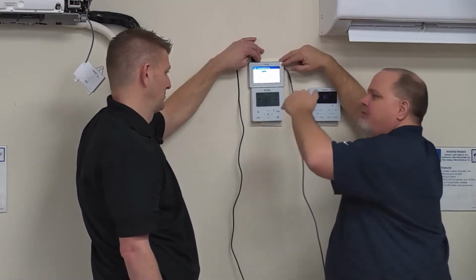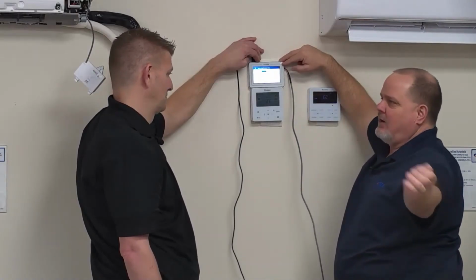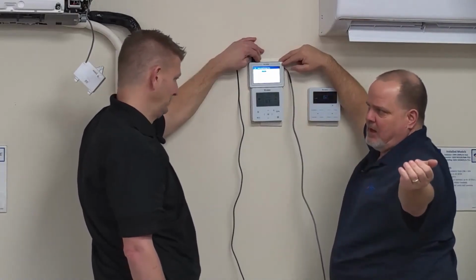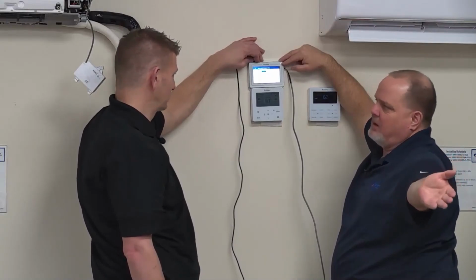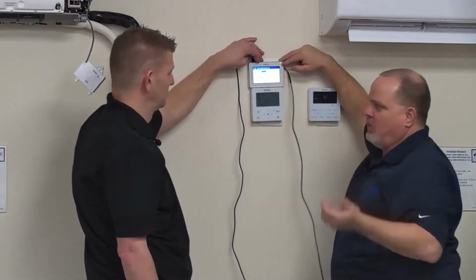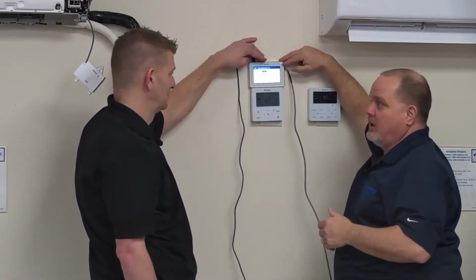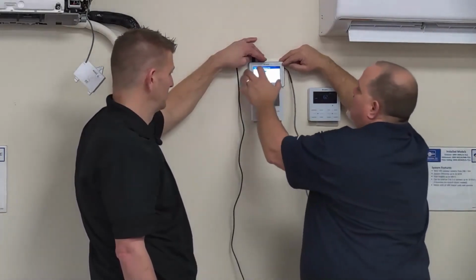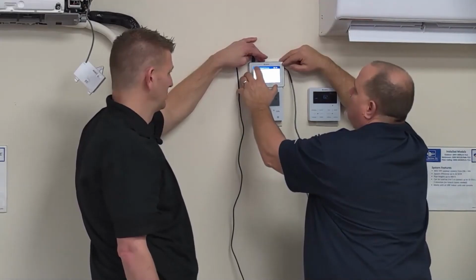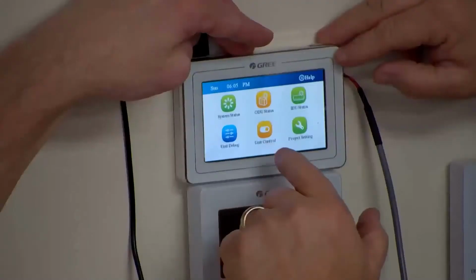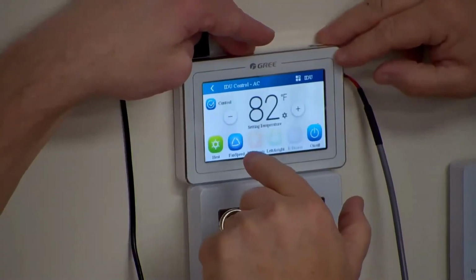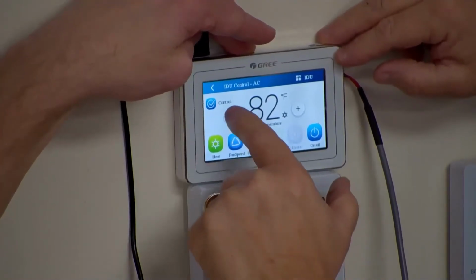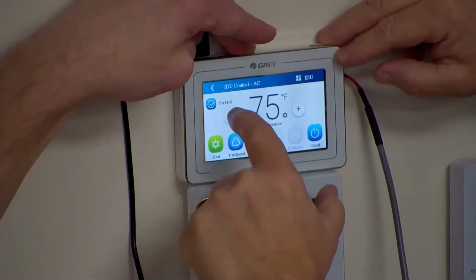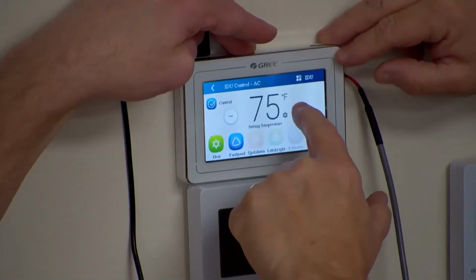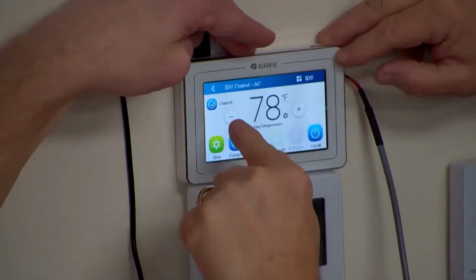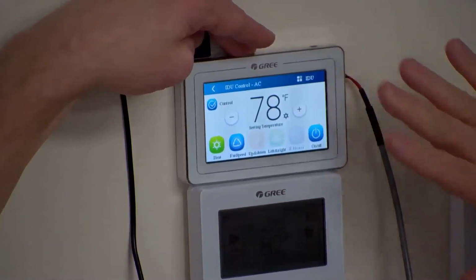But I need that free flow of liquid to go out the other side. I really don't want to be metering refrigerant into my liquid line going back to my outdoor unit from my indoor unit. So that EEV should be wide open or fairly wide open in heating mode, right? So maybe go to unit control and we're going to shut this down. Oh wait a minute, hold on, before we do that, remember I got to hit the check mark to command it.